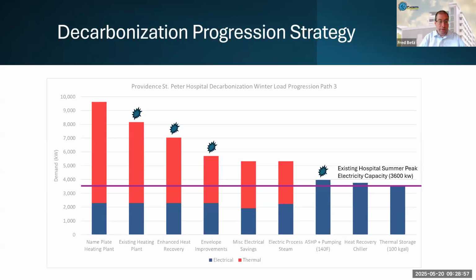And so what we did is looked at the sub-meter data for the entirety of the steam plant and found that it's actually 5 million BTUs less than the capacity. So using the nameplate is about 1.5 megawatts of too much demand. So taking the real data, we're down now to about an 8 megawatt demand in our 3.6 megawatt capacity.